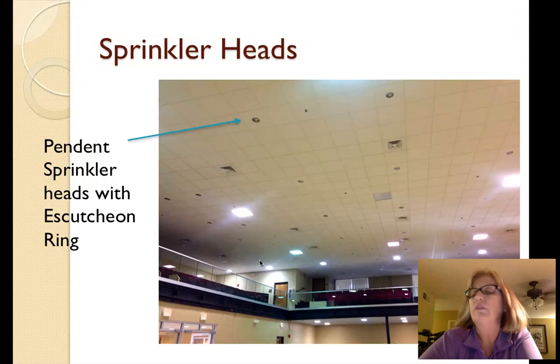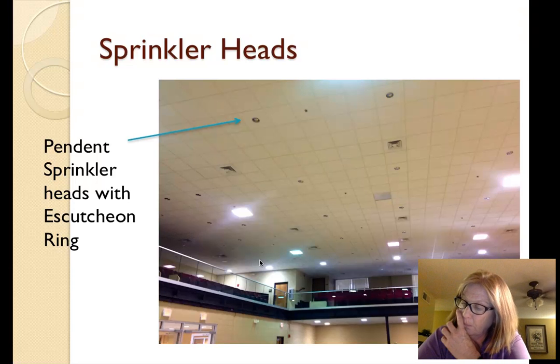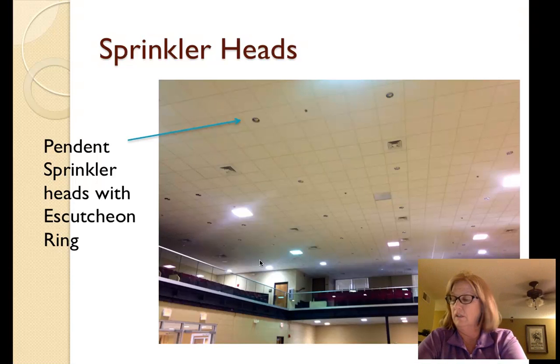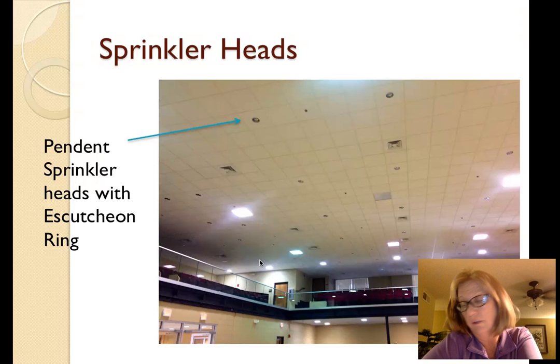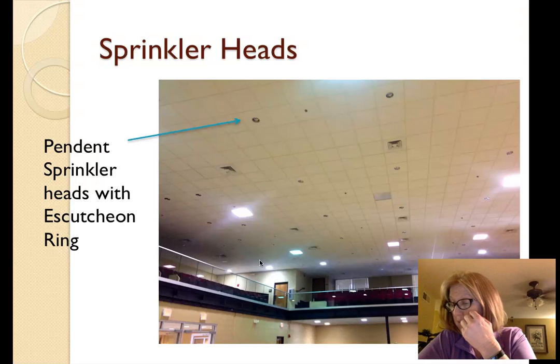He stated that most of the violations that occur with the sprinklers are missing escutcheon rings around the sprinklers. People paint the sprinkler heads and they must be replaced, not cleaned, per NFPA 13. And cover plates are missing on concealed sprinkler heads and have to be repaired.